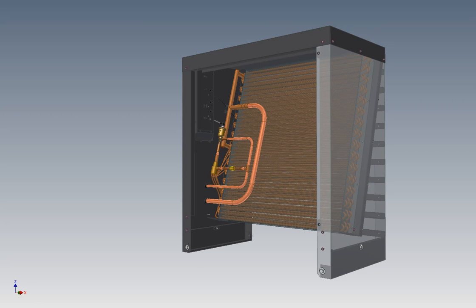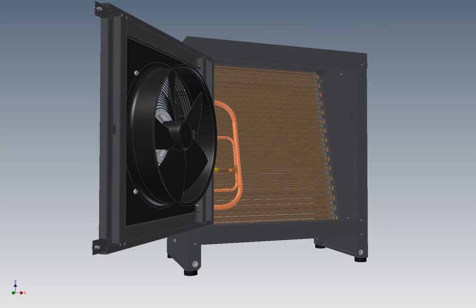We've also used a compact lightweight fan with an EC hub motor. I can show you how the door swings open for easy serviceability — there's a good view of the fan there. This fan enables true variable speed operation based on refrigerant pressure while providing a significant jump in efficiency over traditional PSC type motors.